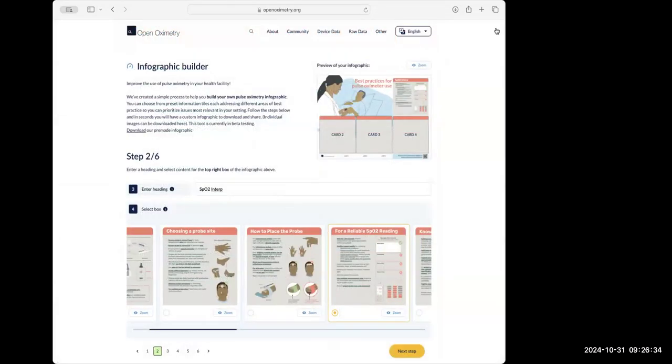I think there was a question we didn't get to from David up above. Did you want to talk about that, David? Sure, yeah. Mostly just wondering, I know on our Masimo devices, if you tap on the waveform or somewhere around there, you can see the perfusion index, which is a nice way to have a numerical representation of how good your signal quality is.